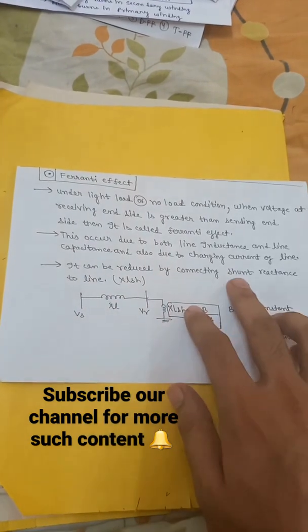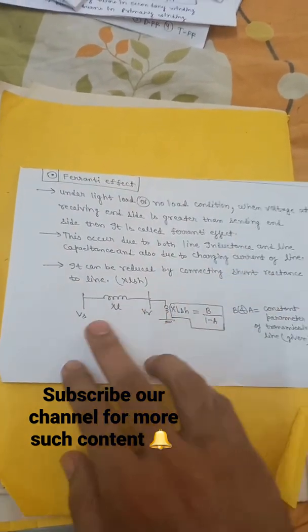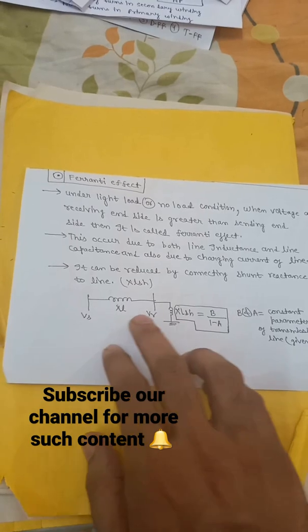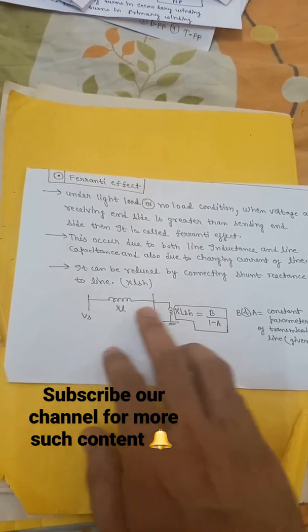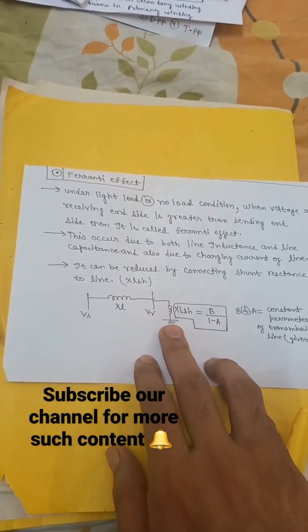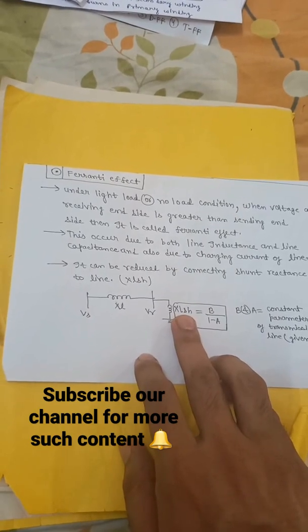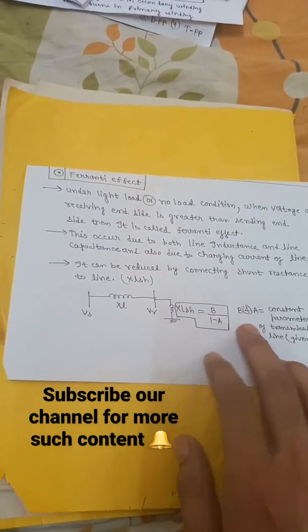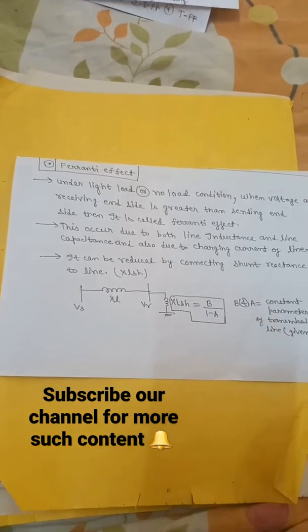And third point is we can reduce this by connecting the shunt reactance across the line. So this is the sending and receiving end, and between that line inductance is there, and where shunt inductance we have connected here. That shunt inductance we are referring it as XLSH, that is equal to B upon 1 minus A, where B and A are the constants of the transmission.